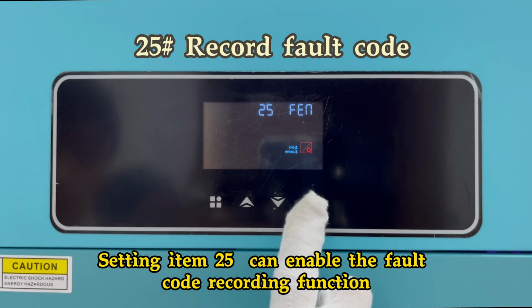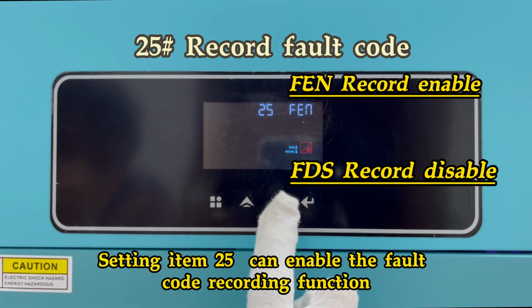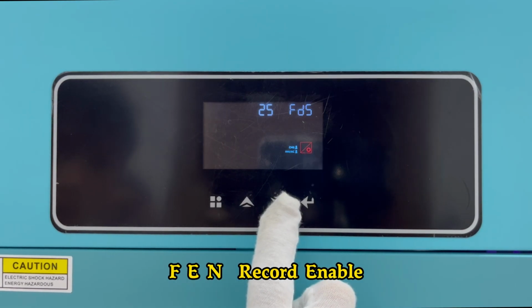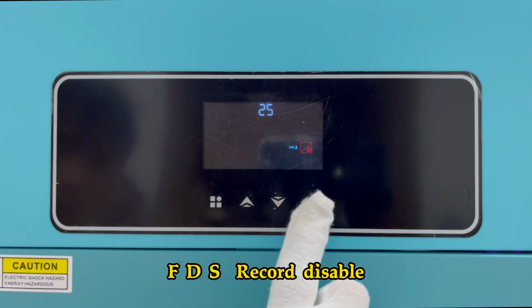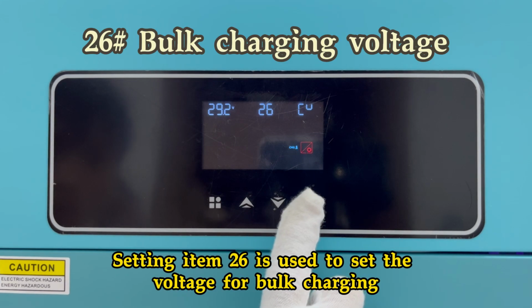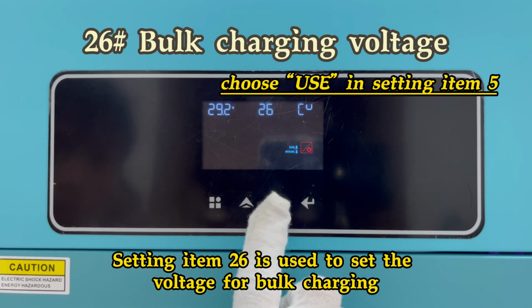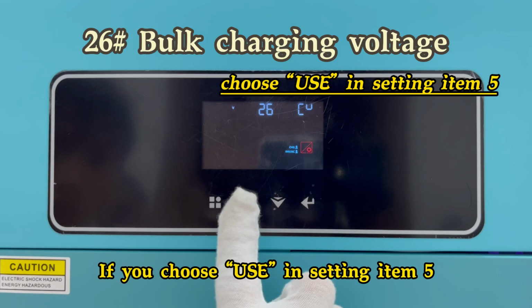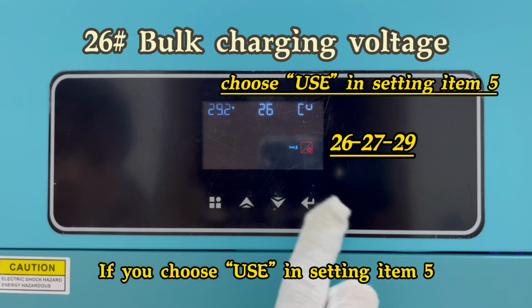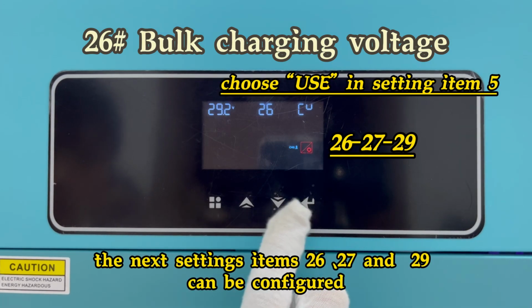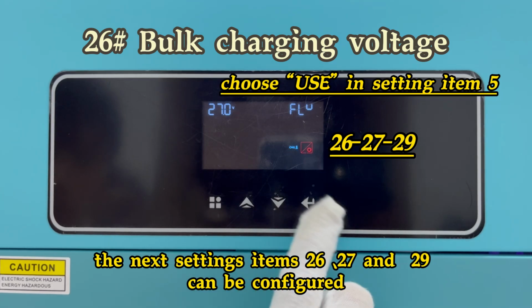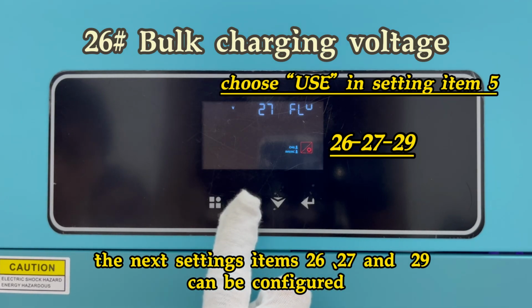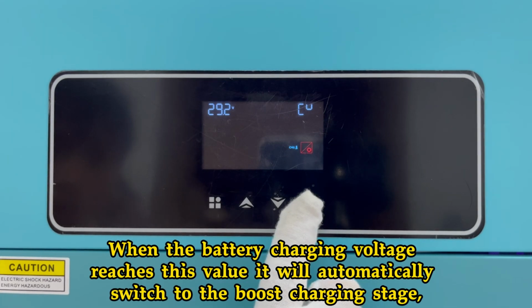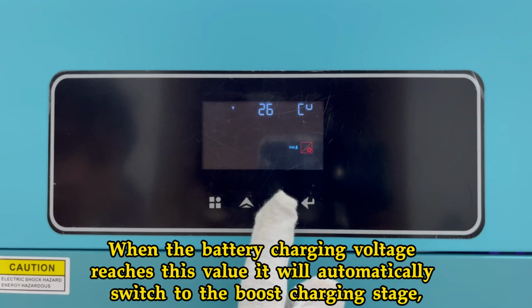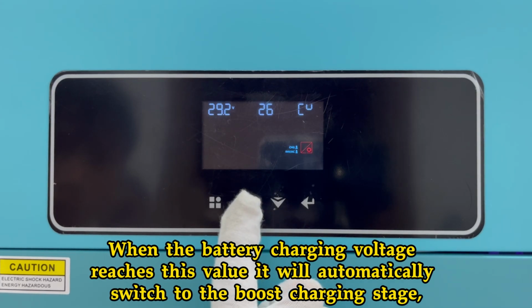Setting item 25 can enable the fault code recording function. FEN record enable. FDS record disable. Setting item 26 is used to set the voltage for bulk charging. If you choose USE in setting item 5, the next setting items 26, 27, and 29 can be configured. When the battery charging voltage reaches this value, it will automatically switch to the boost charging stage.